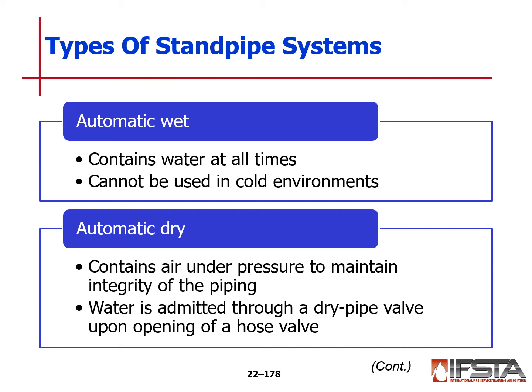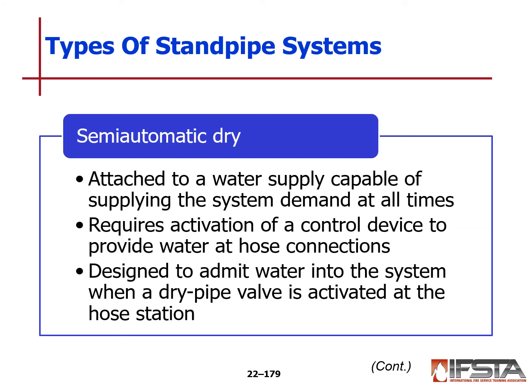Types of standpipe systems: automatic wet systems contain water at all times, and they cannot be used in cold environments. Automatic dry systems contain air under pressure to maintain the integrity of the piping, and the water is admitted through a dry pipe valve upon opening of the hose valve. So it'll work a lot like a dry pipe system. Semi-automatic dry is attached to a water supply capable of supplying the system demand at all times. It requires activation of a control device to provide water at the hose connections. This is designed to admit water into the system when a device is activated at the hose station.